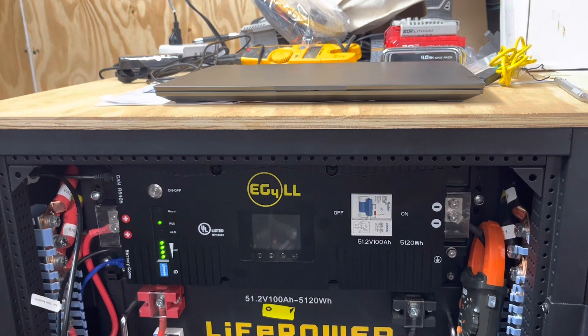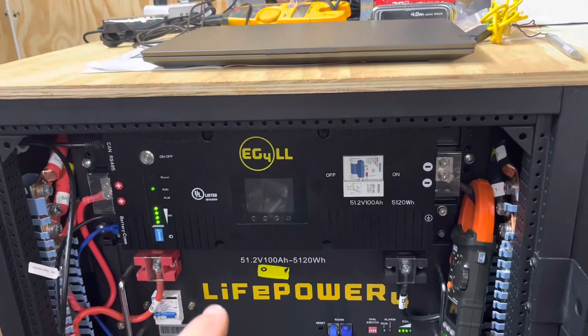You always want your ground tying all your metal components together if you can. That way, if one becomes energized and another one's not, if you touch two different ones, you don't get a potential difference. It's all at the same potential and you don't get shocked. Plus, it helps operate overcurrent protection devices, though it won't operate this breaker unless you get both cables shorted. But I think we're good. I'm not going to run a separate ground wire here, because to get to it, I've got to take my top off and get over to the ground lug. But this is making a good connection.